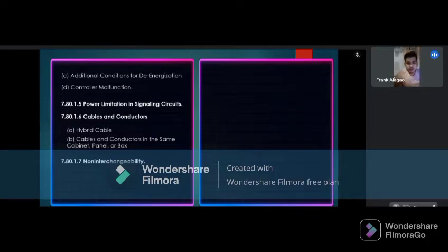So, letter C is additional conditions for de-energization when an alternative source of power is used. In addition to the requirements in 7.8.13B, outlets shall be de-energized when the following conditions occur. The first is the grounded conductor is not properly grounded. Second is any ungrounded conductor is not at nominal voltage. So, next is letter D, controller malfunction. In the event of controller malfunction, all associated outlets shall be de-energized.